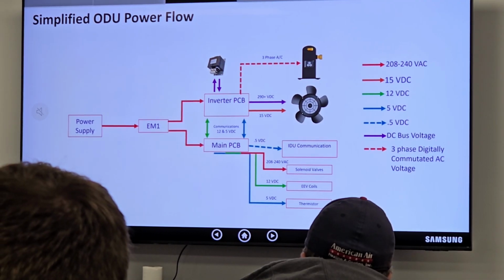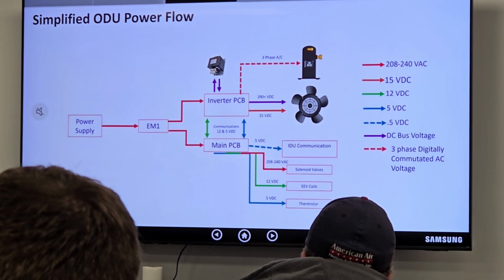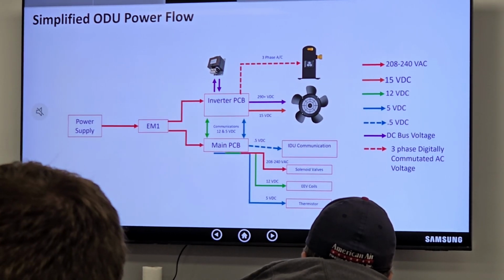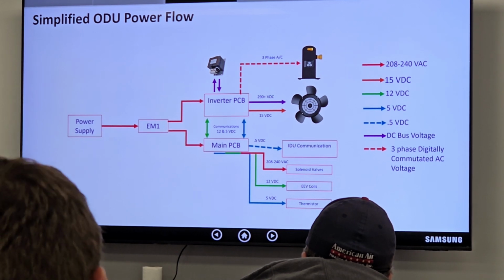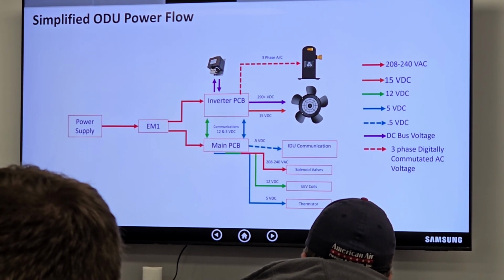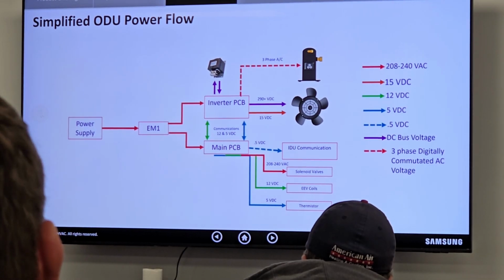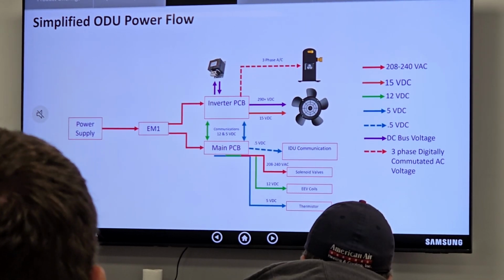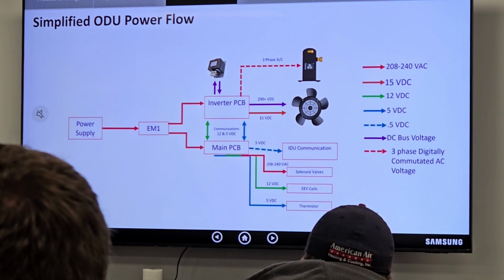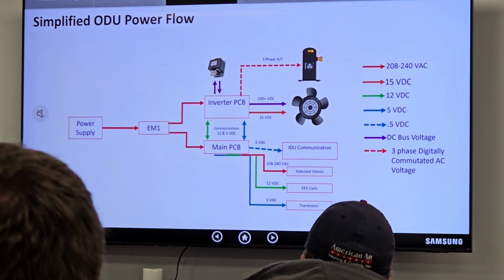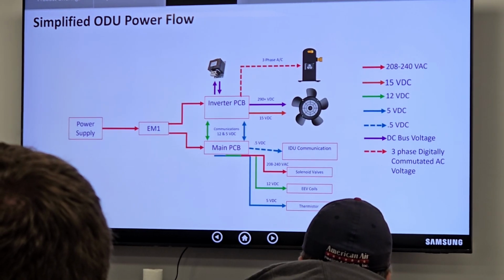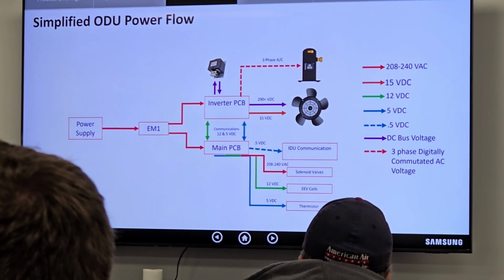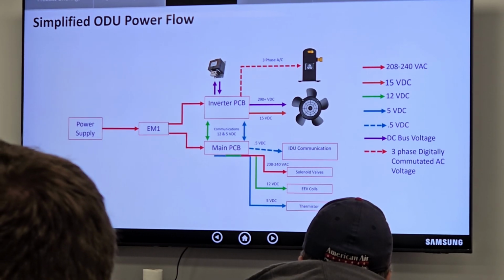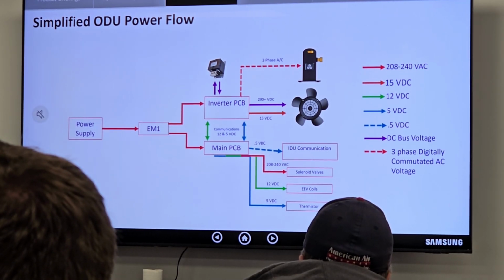Typical mini split wire where you get 3 or 4 wires, we can use that, right? No, sir. Are you talking about like Mitsubishi and everyone else? Yeah. No, sir. You can use the power wire for that, L1, L2 and ground, but we can't skip off and use one of those wires for communication. It just doesn't work. Because Mitsubishi and all of them use a high voltage wire that also feeds a DC voltage through for communication, and we just can't do it. We tried it just to see what would happen. It just won't work. We have to have a separate F1, F2. Okay, so is that on all Samsung installs? Yes, sir. So we need a specific wire for that? For communication, yes, sir. We're in the middle of one right now.